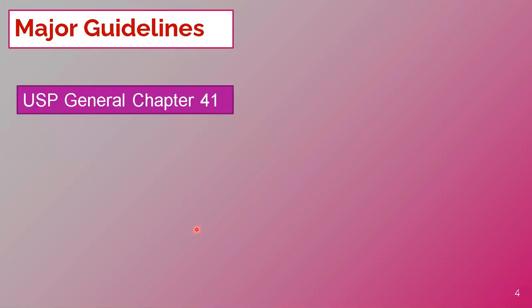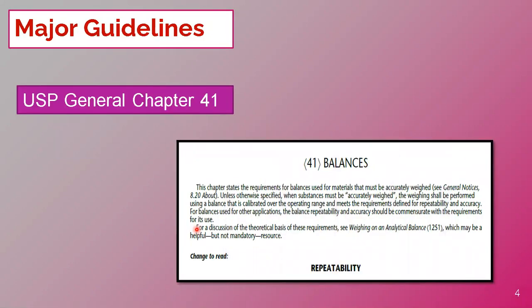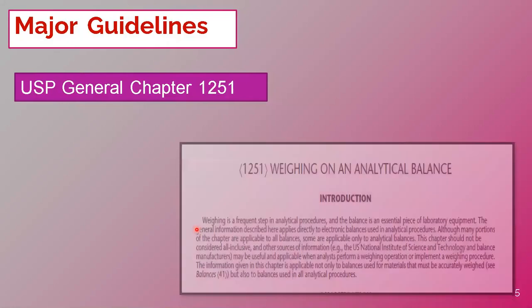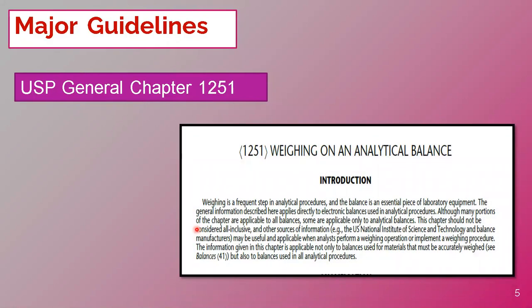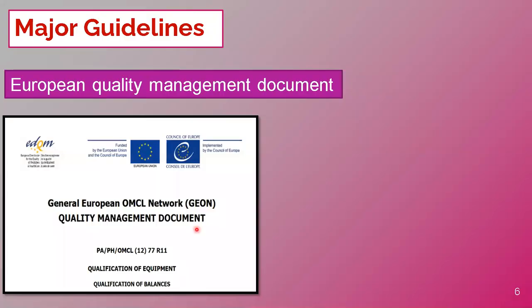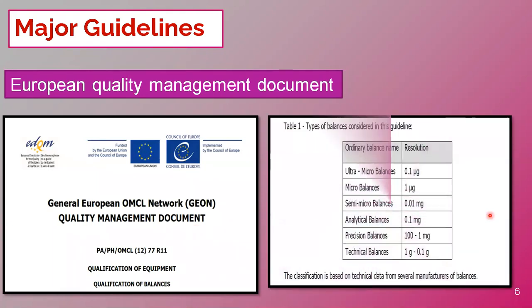The key guidelines are: USP General Chapter 41, which is about balances — whether analytical or any other balance — and USP General Chapter 1251, which gives guidance for weighing on an analytical balance and defines the requirements for balance qualification. Based on classification by manufacturers: ultra micro balance has 0.1 microgram resolution; micro balance 1 microgram; semi micro balance 0.01 mg; analytical balance 0.1 mg; precision balance 1 mg; and technical balance 1 gram to 0.1 gram.